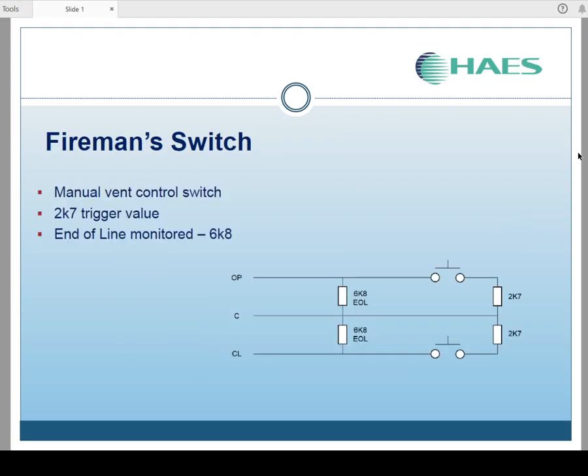The fireman switch input consists of a common, an open and a close. The common and open, common and close are monitored by a 6K8 end of line. And to trigger the input, you'll short or apply a 2K7 resistor across common and open or common and close.